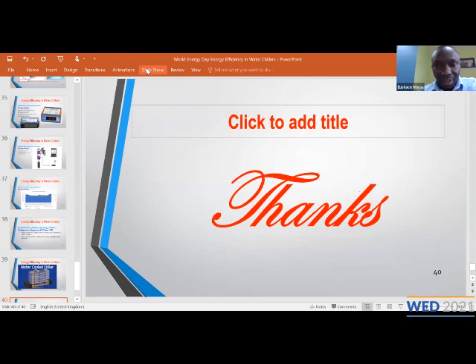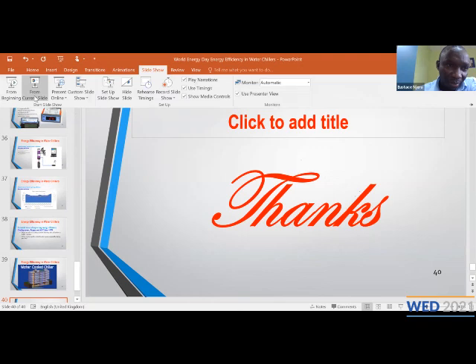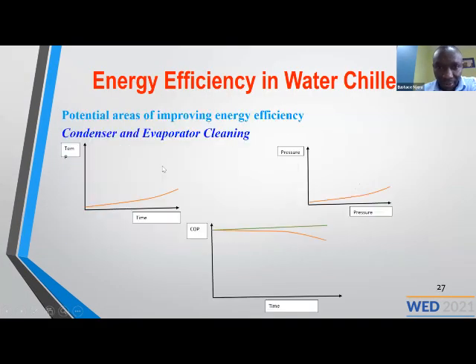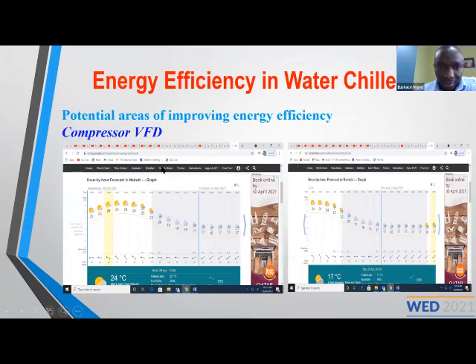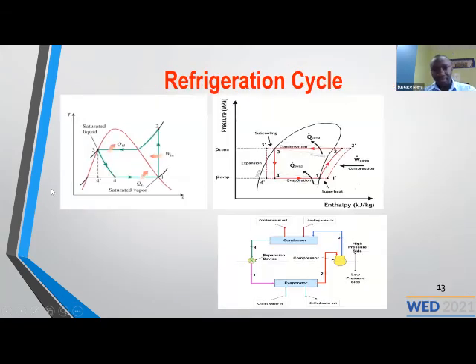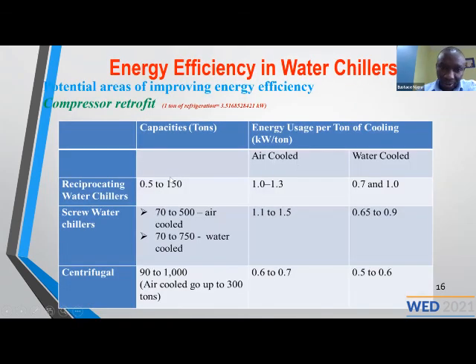Yeah, it's not the amount of air. But it's the cooling load. Cooling load has to do with the amount of heat you have to remove from the service. And this one you can see, it's in the presentation. Although the cooling load will also determine the amount of air you have to use in the fan. This one you can do calculations and use the heat transfer equations to know the amount of air you need to put in, depending on the temperature conditions.